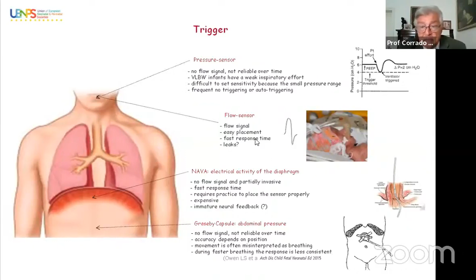But now I'm going to show you our setting. This is a baby treated with synchronized nasal ventilation. Here is the flow sensor. The response time is very good, about 65 milliseconds, and this data is published. We adopted a double inspiratory loop nasal cannula, the same as the iflow nasal cannula, but we developed a cannula of very low resistance, with a very large tube diameter. So we could check that there was really good pressure transmission to the lungs. And I remind you that in this case the nasal prongs must fit well, because the peak inspiratory pressure and the expiratory pressure are controlled by the ventilator.